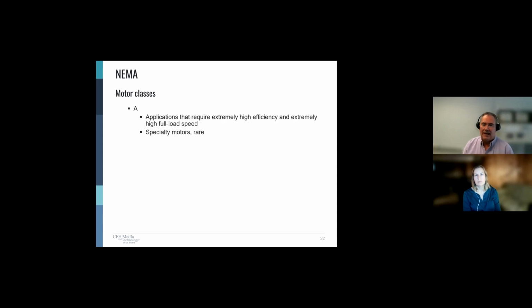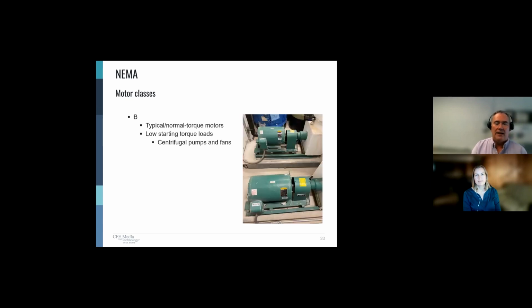So real quickly, class A: extremely high efficiency, extremely high full load speed. They're very rare. They're so rare, I didn't even have a picture of one. I'm kidding. Motor class B, this is more typical: normal torque motors, low starting torque, typically on pumps and fans. It's not a huge locked rotor current type situation. Here's a pair of chilled water pumps. I think these are about 5 or 7.5 horsepower.